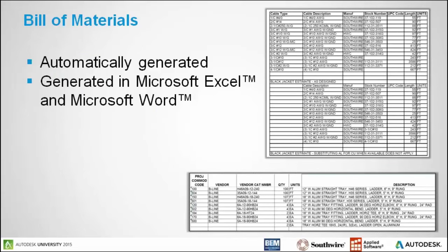Since we've done all of our cable routing and raceway system in a database, we can generate bills of material. The program will allow you to specify a cable tray manufacturer and get specific manufacturer catalog and part numbers. Same thing with the cables. This example is using B-Line tray and Southwire cable. By the way, it will also work with individual single conductor cables routed in conduit, and we can color code those as well.